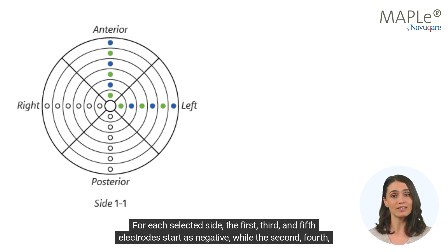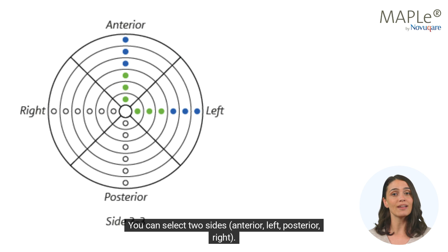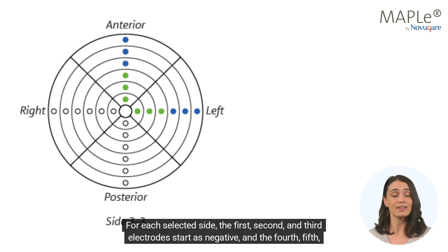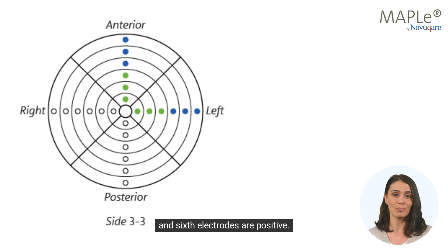For each selected side, the first, third, and fifth electrodes start as negative, while the second, fourth, and sixth electrodes are positive. Side 3. You can select 2 sides, anterior, left, posterior, right. For each selected side, the first, second, and third electrodes start as negative, and the fourth, fifth, and sixth electrodes are positive. Note, since MAPLe uses a biphasic symmetrical curve, the polarity switches halfway through the stimulation pulse. Negative becomes positive and vice versa.